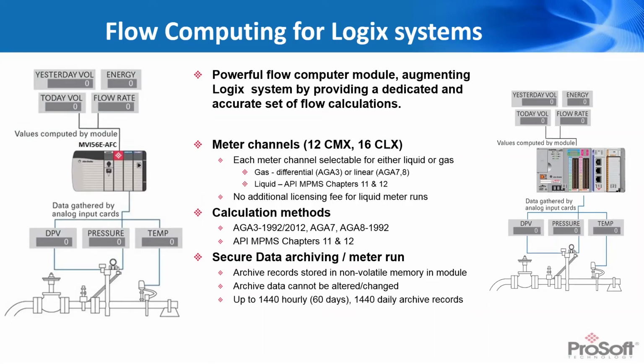And so that's one of the main reasons that some customers were doing this all in standalone flow computers, just the archiving capability. And when you talk about API requirements, I mentioned earlier that you had to support a minimum of 35 days worth of hourly and daily records. And we support up to 1,440 hourly records, which is 60 days, as well as the same 1,440 daily records, which is just under 4 years worth of archive capability right there.